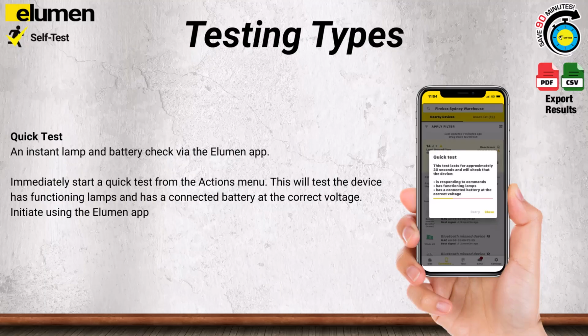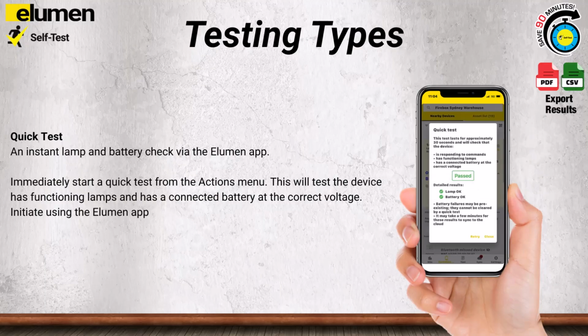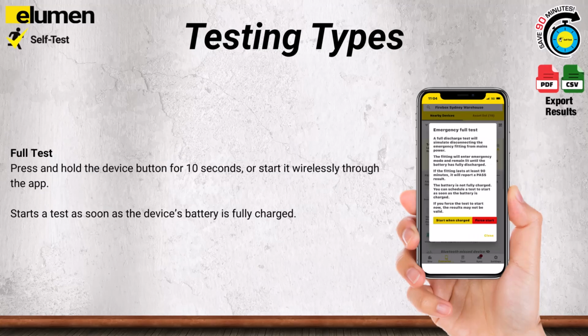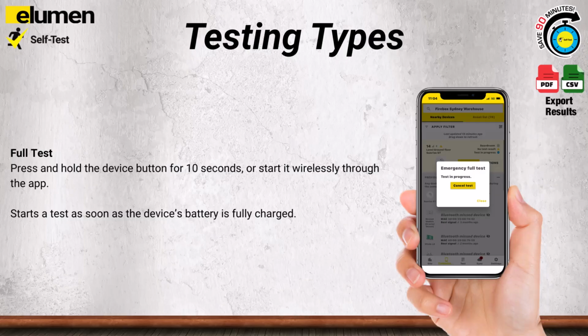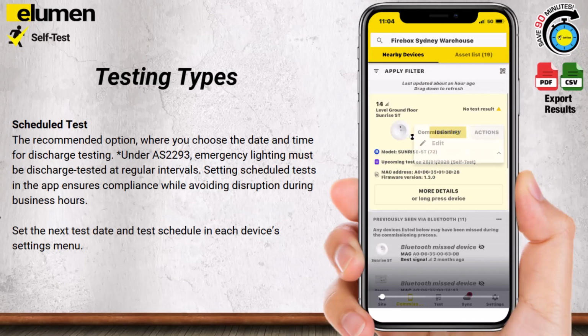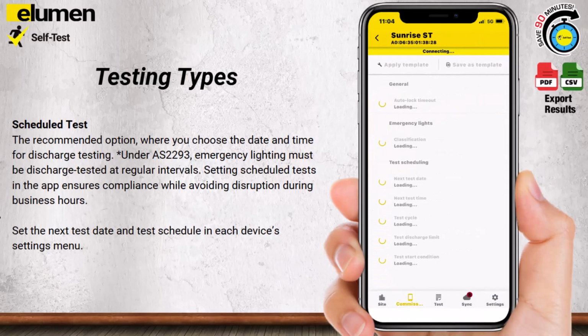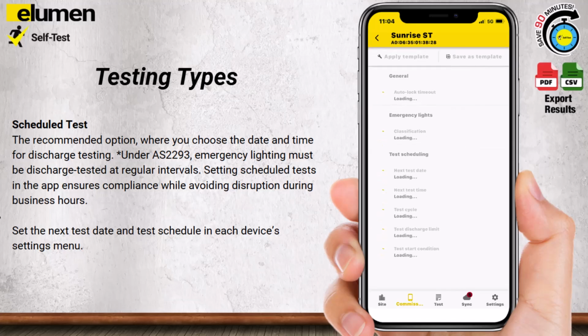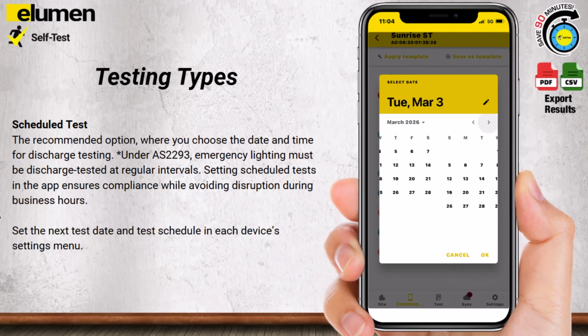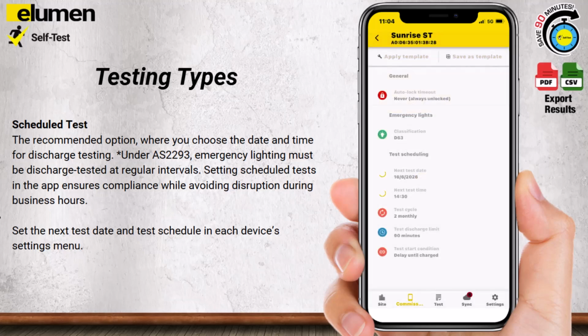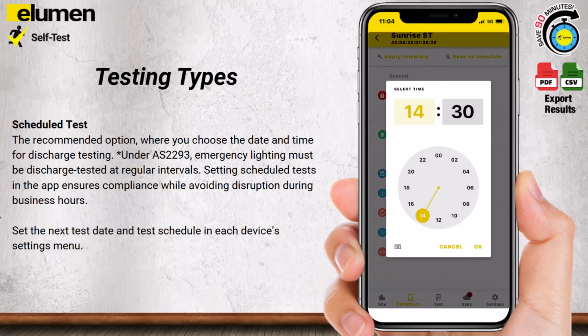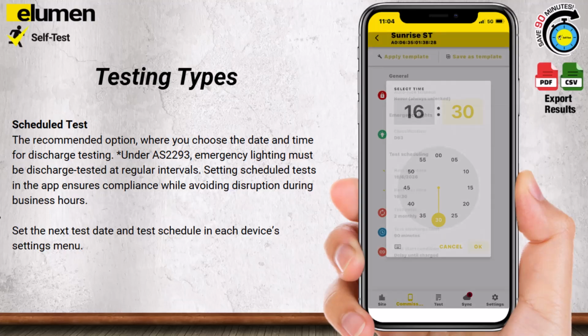There are 3 main ways to test. Quick test, an instant lamp and battery check via the Elumen app. Full test, press and hold the device button for 10 seconds, or start it wirelessly through the app. Scheduled test is the recommended option, where you choose the date and time for discharge testing. Under AS2293, emergency lighting must be discharge tested at regular intervals. Setting scheduled tests in the app ensures compliance while avoiding disruption during business hours.